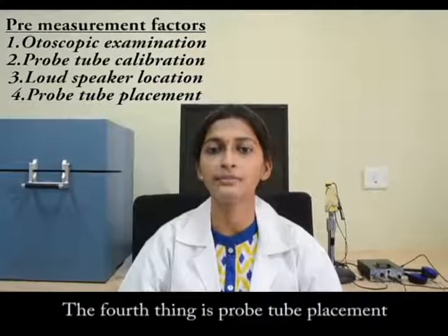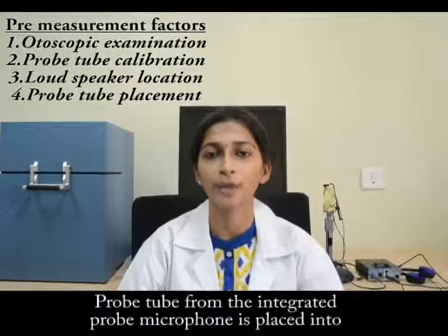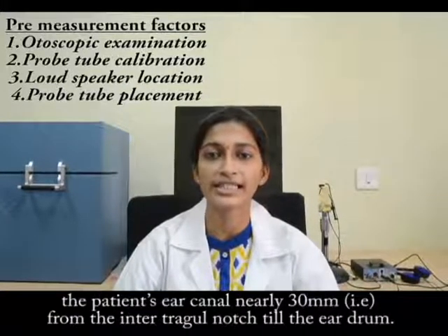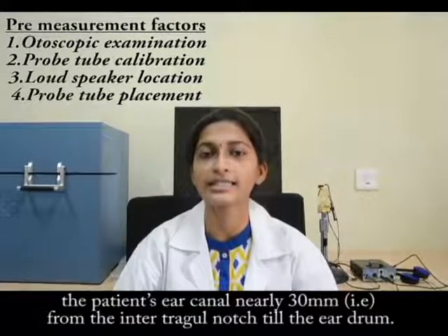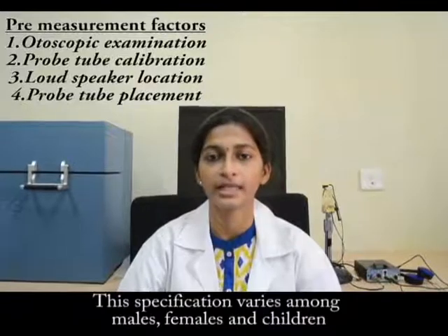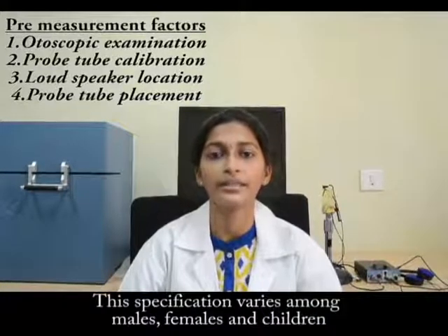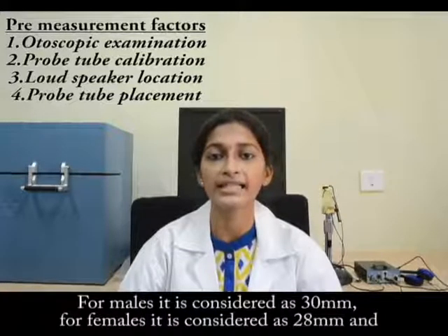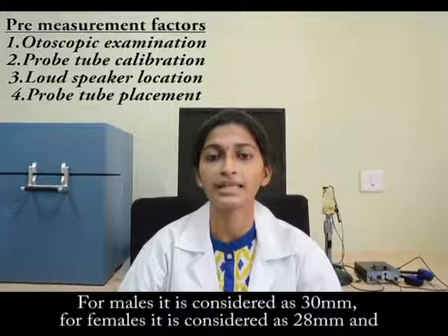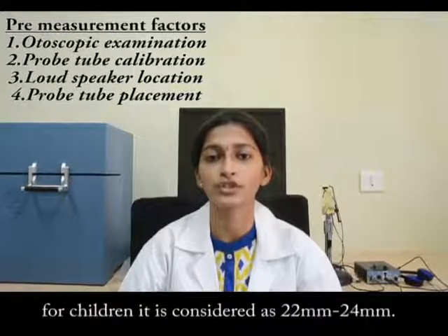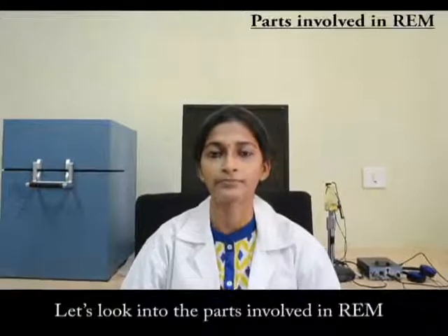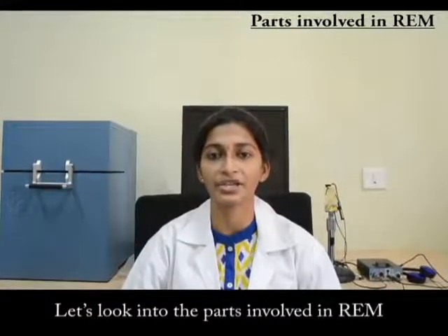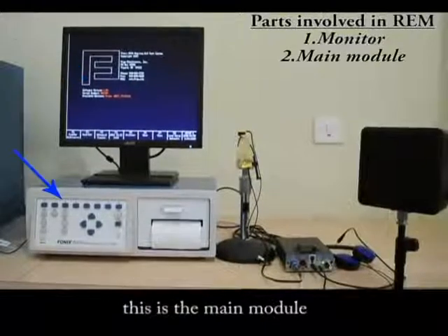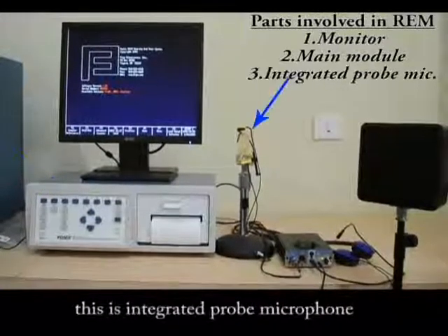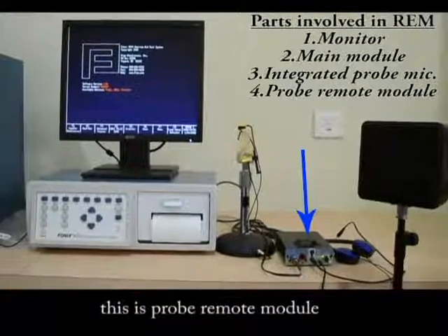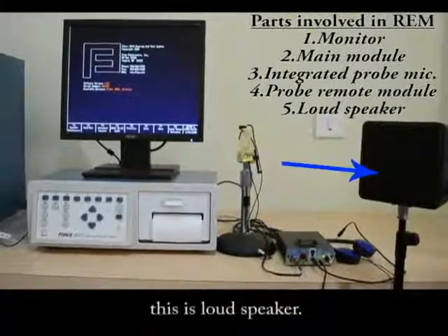The fourth thing is the probe tube placement. The probe tube from the probe microphone is placed into the patient's ear canal nearly 30 mm, that is from the intertragal notch till the eardrum. This specification varies among males, females and children. For males it is considered as 30 mm, for females it is considered as 28 mm and for children it is considered as 22 to 24 mm. Let's look into the parts involved in real ear measurements. This is the monitor, this is the main module, this is the integrated probe microphone, this is the probe remote module, and this is the speaker.